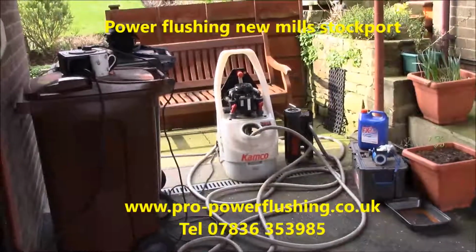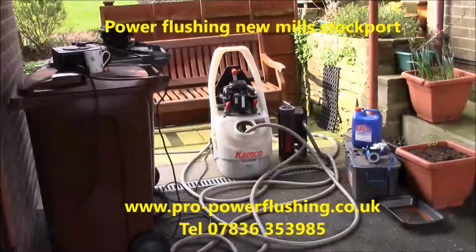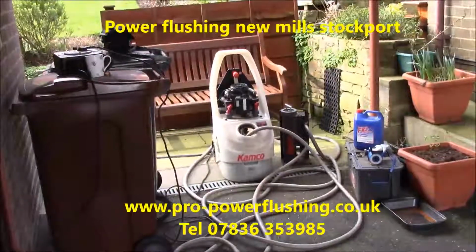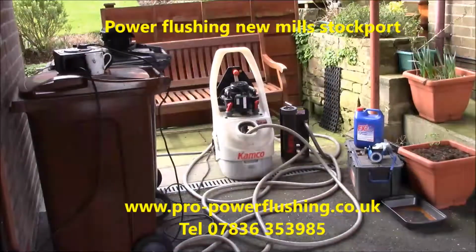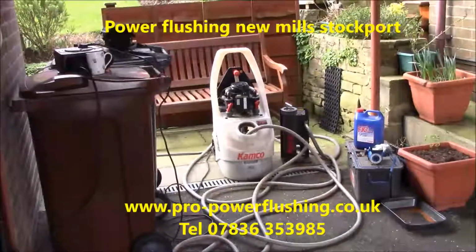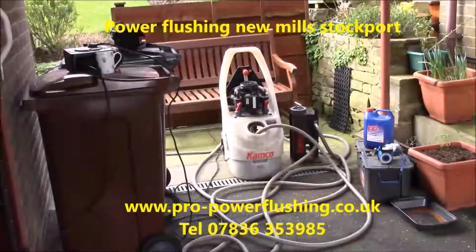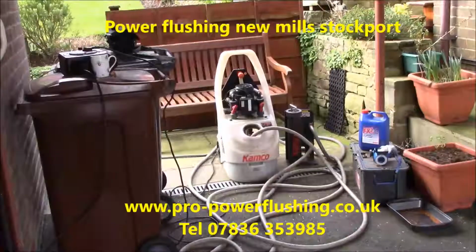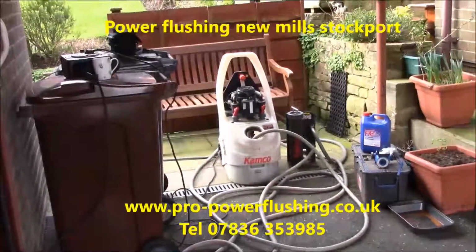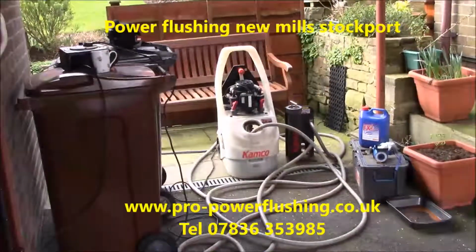We had to cut one of the pump valves off. It had been on there about 30 years. So we cut that off and we're hooked in. The first thing we noticed was an absolute load of air in the system. So whatever British Gas did, they didn't actually do it right. But anyway, we've got all that air out of the system. We're going to clear that blockage coming down from the header tank, and we're going to get this customer some heat in the radiator system and stop all the noises she's been hearing, a lot of banging and everything. Obviously that's corrosion and air in the system. We're getting a great flow around the system now.